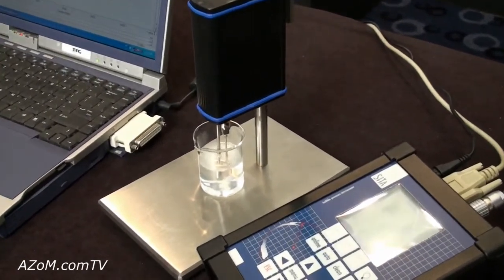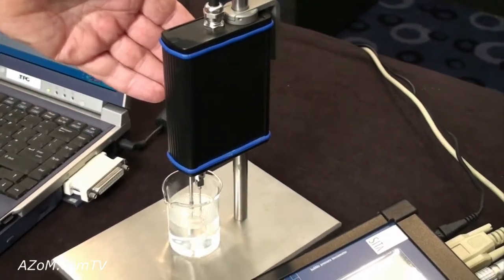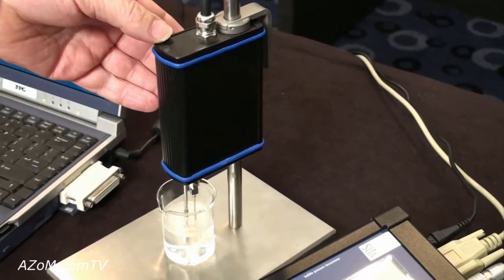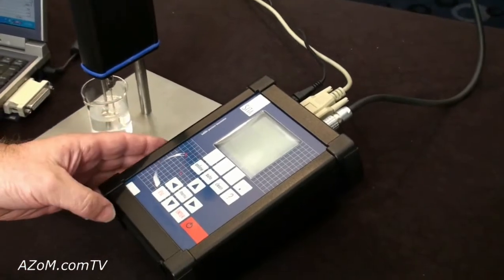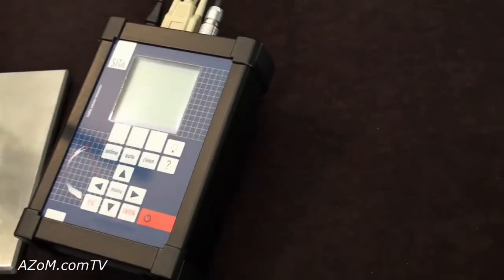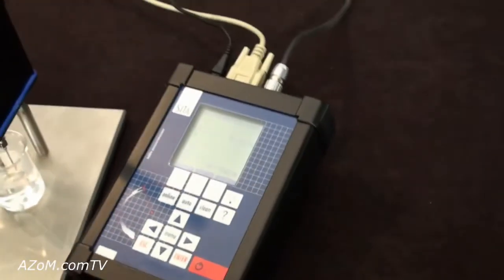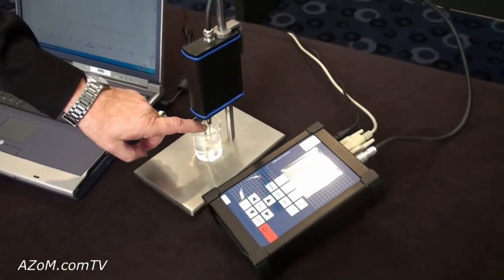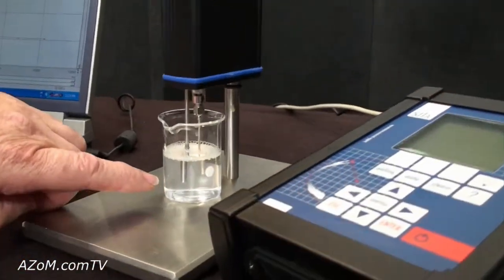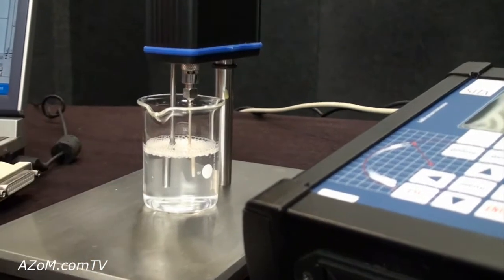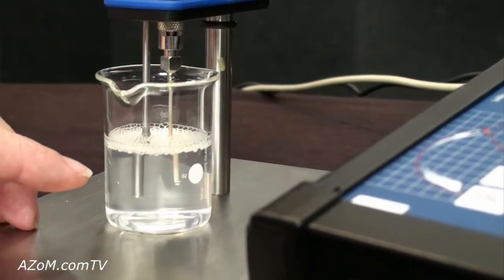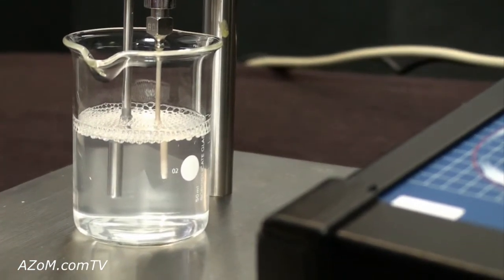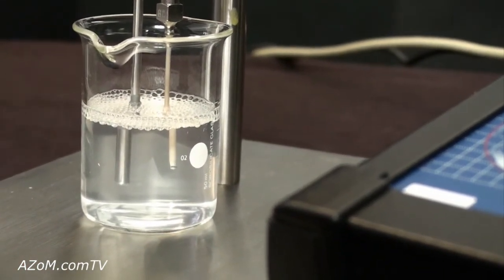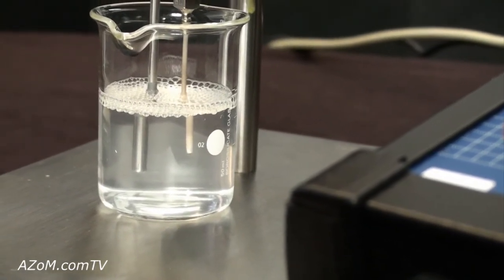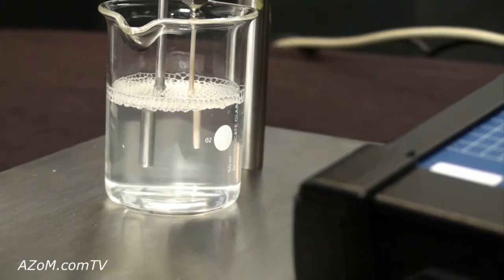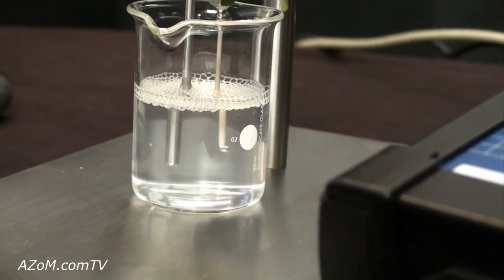Now, if we have a look, we have a measurement head here, which has a high resolution pressure transducer inside it, and we have a pump and control unit with a display here on the right hand side. Basically, the pump pumps air through the measurement head and outer capillary tube here, and you can see periodically there's a bubble that comes out of the end of the tube. We measure the pressure inside that bubble as it forms around the end of the tube and releases, and the pressure differential we can convert mathematically into surface tension. So that's basically what the instrument does.